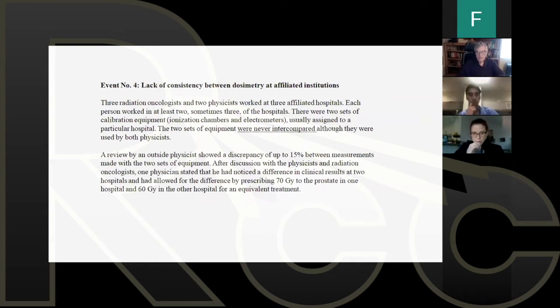So an independent physicist found a discrepancy of 15% between measurements made with the two sets of equipment. Each set of equipment was assigned to a clinic. So they were never mixed. They were never sent from one clinic to the other just to see if the results were the same. They were never intercompared. Interestingly, after discussion with the physicist and the radiation doctor, the physician actually said that he had noticed the difference in clinical results between the two hospitals. And he corrected for that by prescribing 70 gray instead of 60 gray.